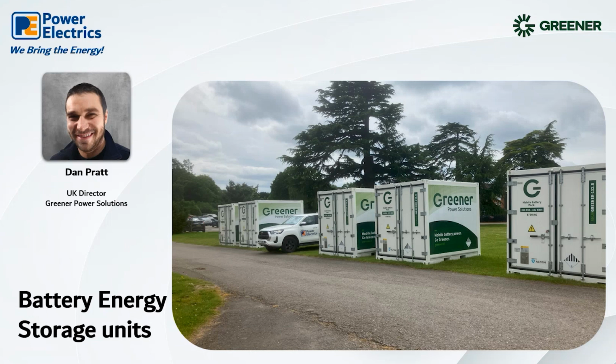The technology's moved on. The technology's there. When we have multiple batteries running in parallel, they effectively become one, just as 500 kVA diesel engines running in sync is the same. The benefit of looking at that principle and applying it to battery systems is you have all of that peak power available whenever you want it without having large engines running all the time. Okay, that was a good question.